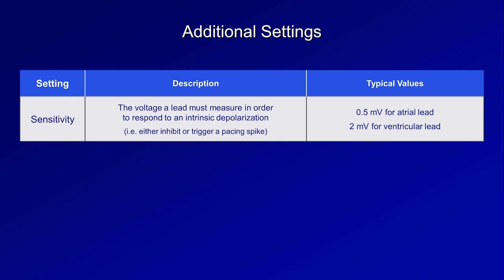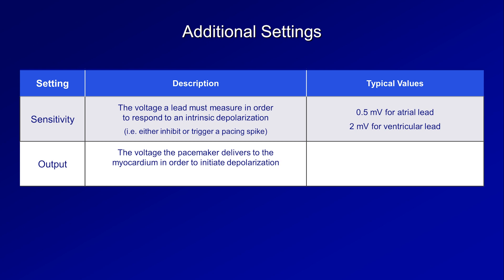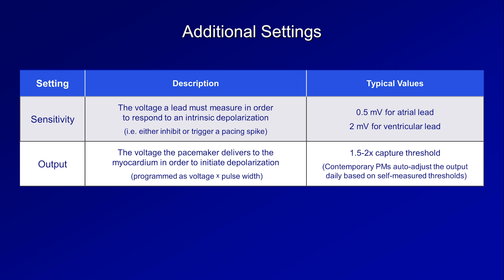In contrast to all other settings discussed, lead sensitivities are usually not changed once the pacemaker has been implanted. The output is the voltage the pacemaker delivers to the myocardium to pace the heart. The ability to initiate depolarization depends on both voltage and pulse width — the higher the voltage, the shorter the pulse width needs to be. Output should be high enough to pace 100% of the time the pacemaker intends to, but not so high as to unnecessarily waste battery life. Typical output is 1.5 to 2 times the threshold at which the pacemaker can initiate depolarization, known as capturing the heart. Contemporary pacemakers auto-adjust output daily based on self-measured thresholds to ensure capture.